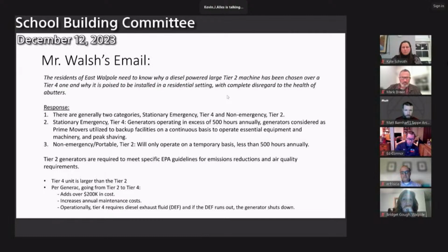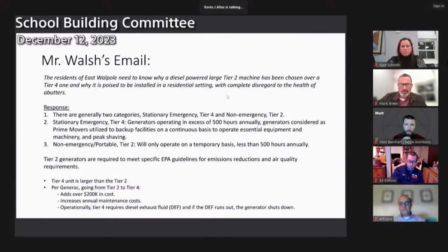And again, the certifications from the manufacturer identifying that was shown on the previous slide, as well as, I don't know if it's the next slide, the fuel source, the low sulfur fuel that was implemented by the EPA, again, to help the emissions for tier 2 generators as well as tier 4 generators. But again, the EPA has set guidelines, and these generator manufacturers have met these guidelines, as well as the fuel sources that they're using. And just a couple of other footnotes: the tier 4 unit is much larger than the tier 2. And then this from one of our generator suppliers, going from a tier 2 to a tier 4 would have added over $200,000. That would have been material cost only, and would increase the annual maintenance cost.